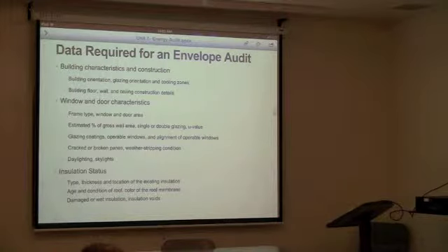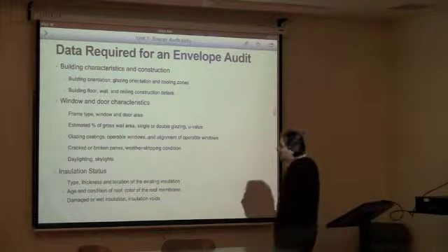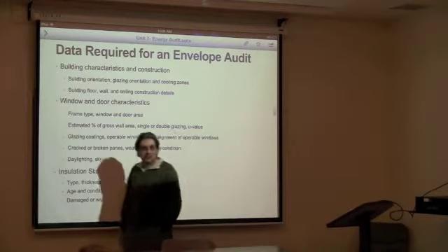So in California, if I audit this building and I find all of the windows are single glaze, I'm not going to put a recommendation that you need to make this double glaze. Because it's a lot of money to spend, you don't gain that much. But if this building is in Minnesota, it's very important. You have to make it double glaze, right? So location of the building is very important. How many windows you have, how many doors you have, what is the insulation status.